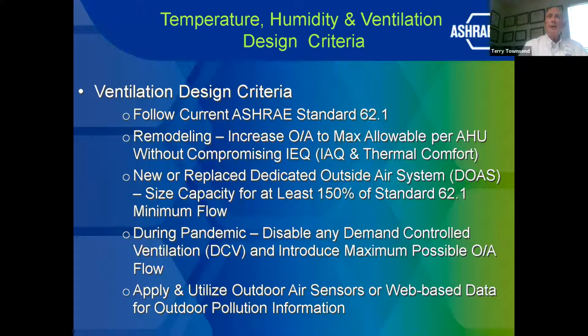Okay, ventilation design criteria, again, follow 62.1, and remodeling, increase outside air to maximum allowable for each air handler without compromising indoor environmental quality. That's IAQ, thermal comfort. New or replace dedicated outside air system, size it for at least 150% of the standard 62.1 minimum flow. And during this pandemic, disable any demand control ventilation and introduce maximum possible outside air ventilation if possible. If it is not occupied, don't have it on. And then utilize outdoor air sensors or web-based data for outdoor pollution information. Let this be a part of your control factor.